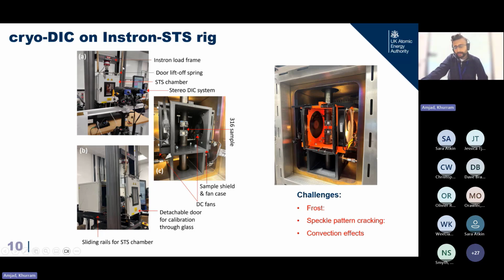So the Instron STS rig that we have, we have spent a significant amount of time trying to deploy DIC on it, and there are some challenges with it. The first is because it's not a vacuum chamber, we have an issue of frost. The way it works is that it has the inlet for liquid nitrogen, which by the time it comes to the chamber is in a gaseous form, and there is a fan at the back which circulates this cold gaseous nitrogen into the chamber. So you get convection effects, which affect your optical measurements. So that was a challenge.